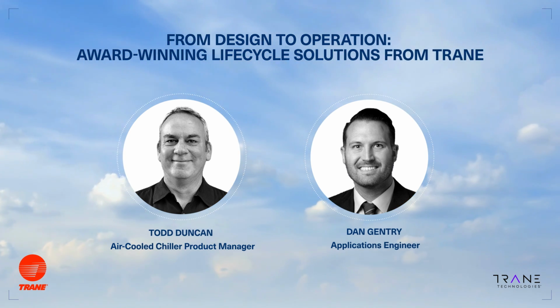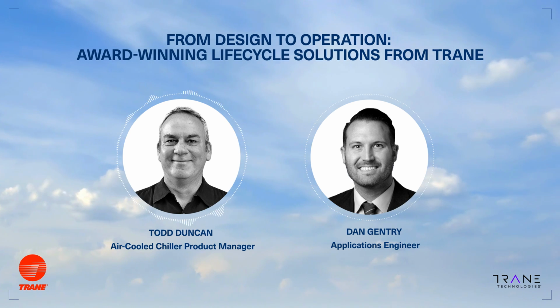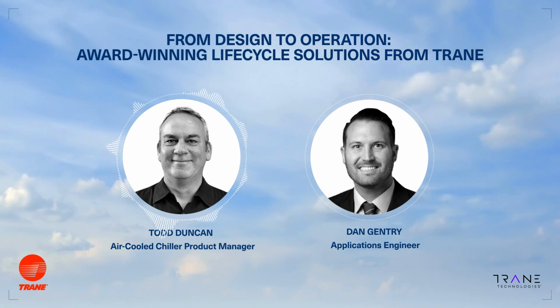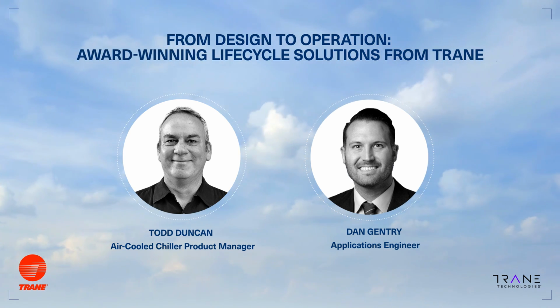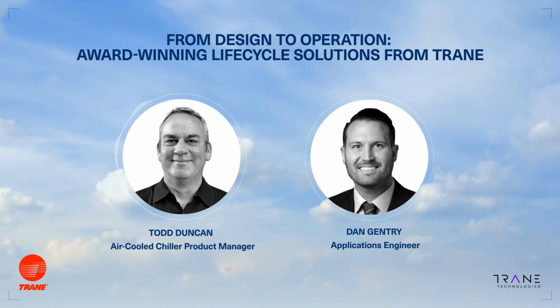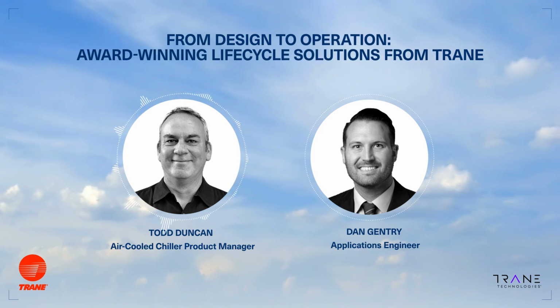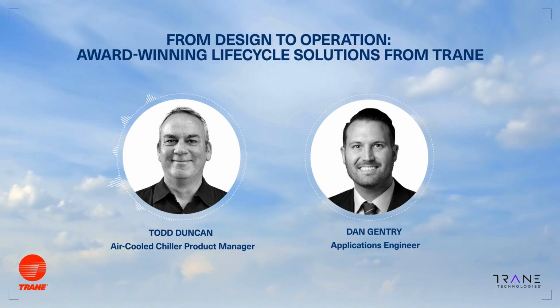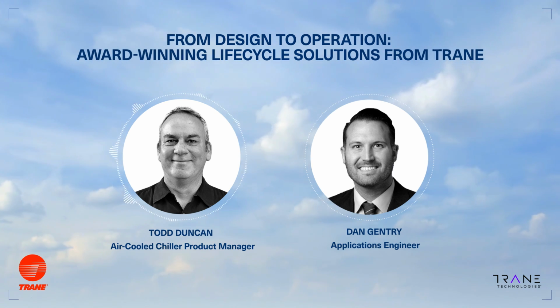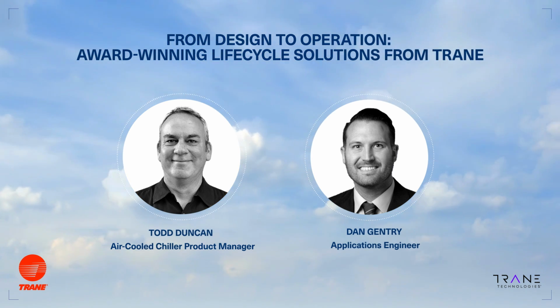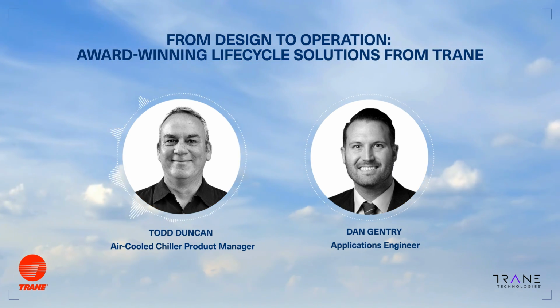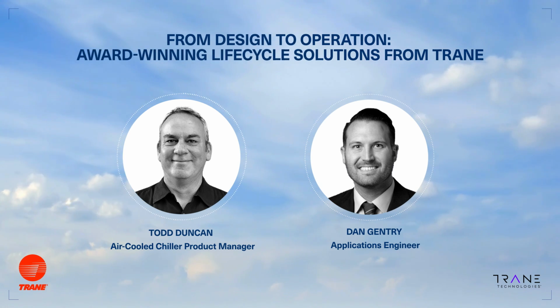Yeah, the Model ACX is an air-to-water heat pump. Air-to-water heat pumps are pretty simply a traditional air-cooled chiller that uses a reversing valve to operate in reverse. In the summertime when we're cooling the building, cooling operation is the same as a traditional air-cooled chiller.